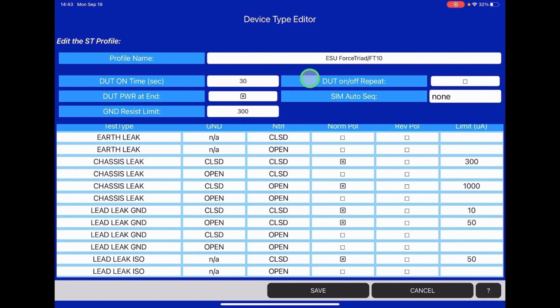The next field is DUT on-off repeat, which is, do you want to repeat the electrical safety testing twice on the unit, once with it off and again with it on? In our case, we only need to do it once with the unit on, so we'll leave this unchecked. The next field is DUT power at end, which is, do you want the ESU to stay powered on at the end of the safety test so that we can do functional tests? I always suggest enabling that and having that checkbox on.